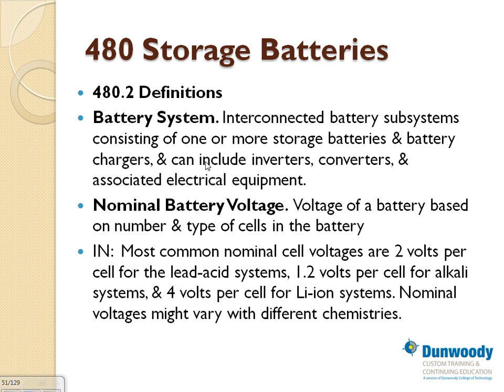Okay, and then they have the definition of that, and they give a couple of voltages of the batteries based on the number and the type of the cells, and they have a couple of examples. IN is information note. If you're not familiar with it, is anybody familiar with the term fine print note? If you're not familiar with it, don't worry about it, it's gone. They changed it only in 2011 to call it IN, informational note. So they're just explaining how they calculated the voltage based on 2 volts per cell for one type, or 1.2 volts for another type, or 4 volts for a third type. So based on how you make the batteries, you can find the cells based on the batteries.